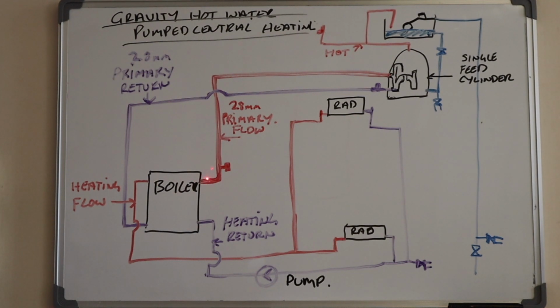We now have the flow and the return on opposite sides of the heat exchanger. And the reason why we used to do that is so we made sure we used all the heat exchanger, because if we just put the return on the same side here, we would be short circuiting round here. So we used to always put them on the opposite side, so you can see that's the flow for the cylinder, that's the return, sorry, for the cylinder, that's the flow for the heating, that's the return for heating. So they would use the full heat side of the heat exchanger.